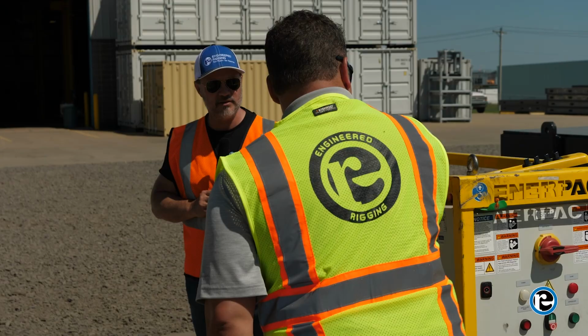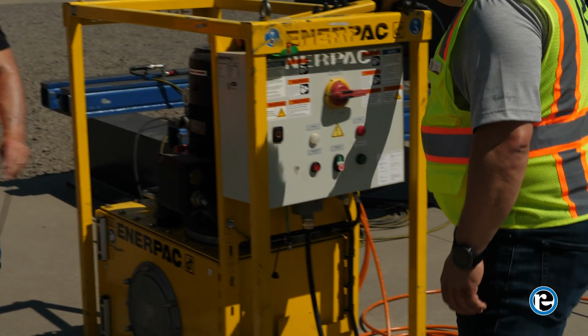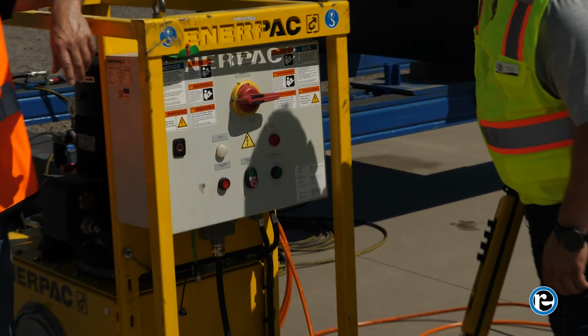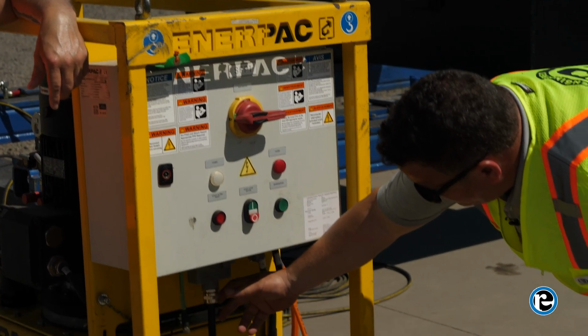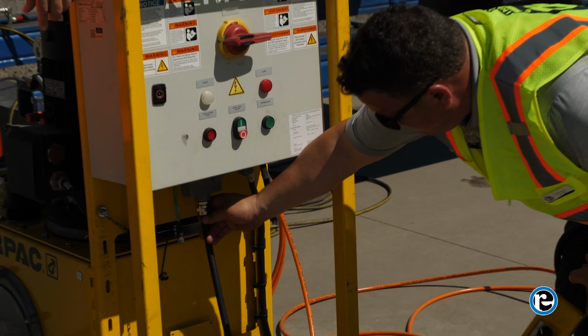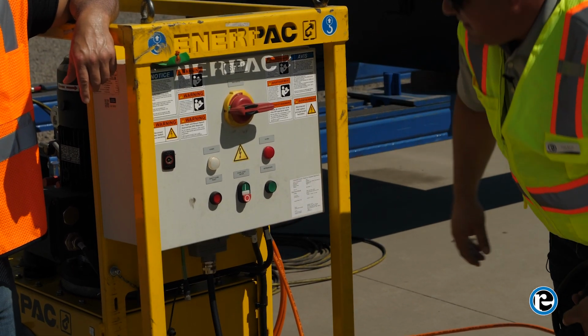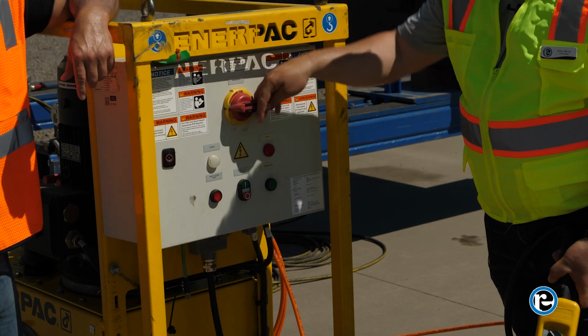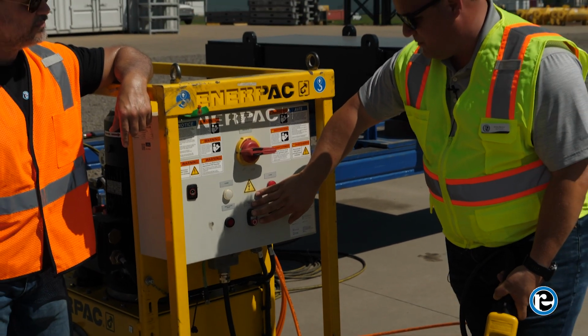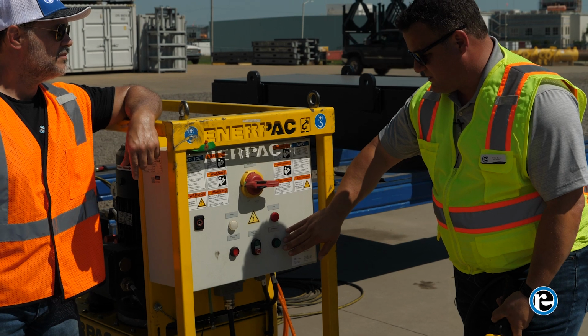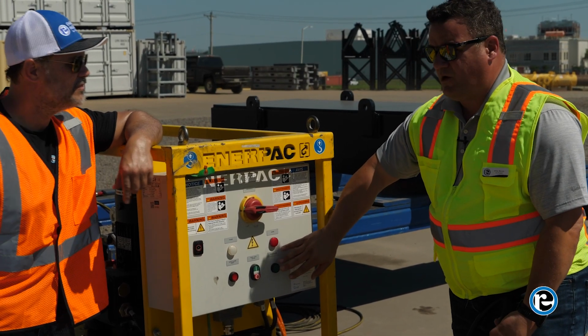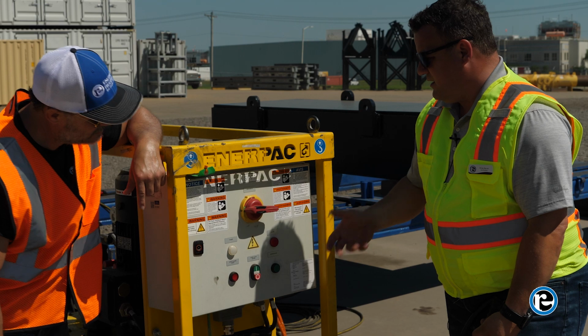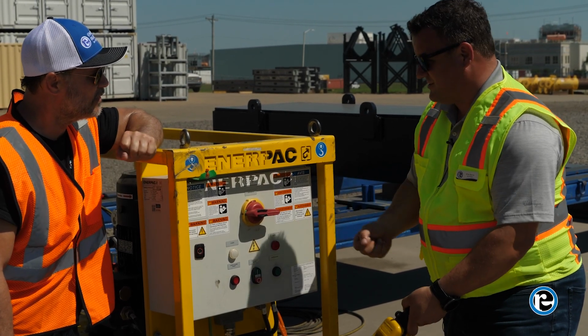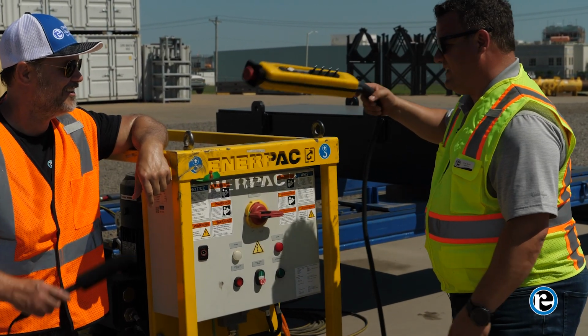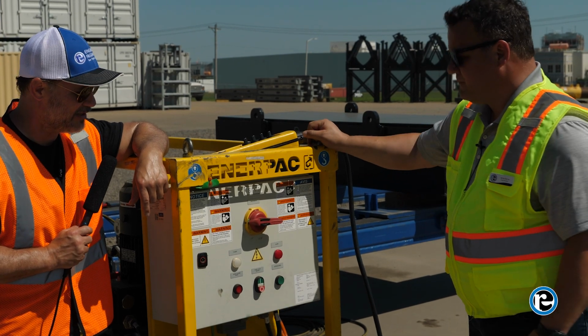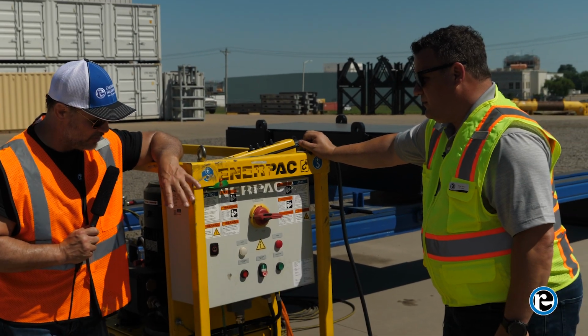So where does that plug in? If we look over here on this side of the pump, we've got the electrical panel, so our power runs up into here. The pendant actually moves into the bottom of the electrical panel here, and this is where we have the ability to turn on the power for the pump and also start the motor, reset any safety alarms that we might have. When we're done, we can depressurize the system so that the hoses that might be sitting out in the hot Arkansas sun don't get pressurized up on the couplers.